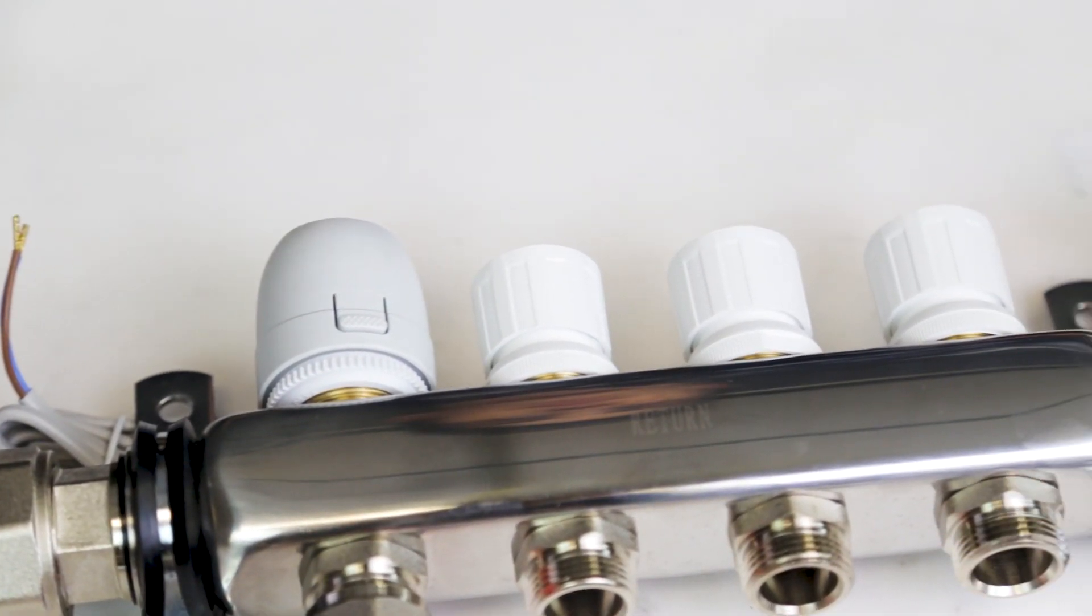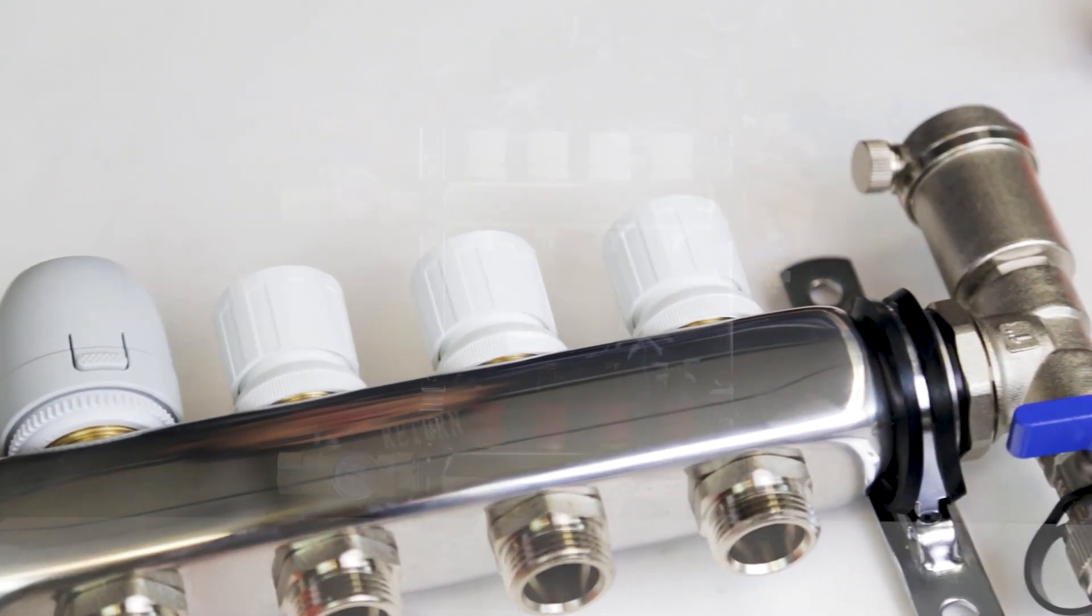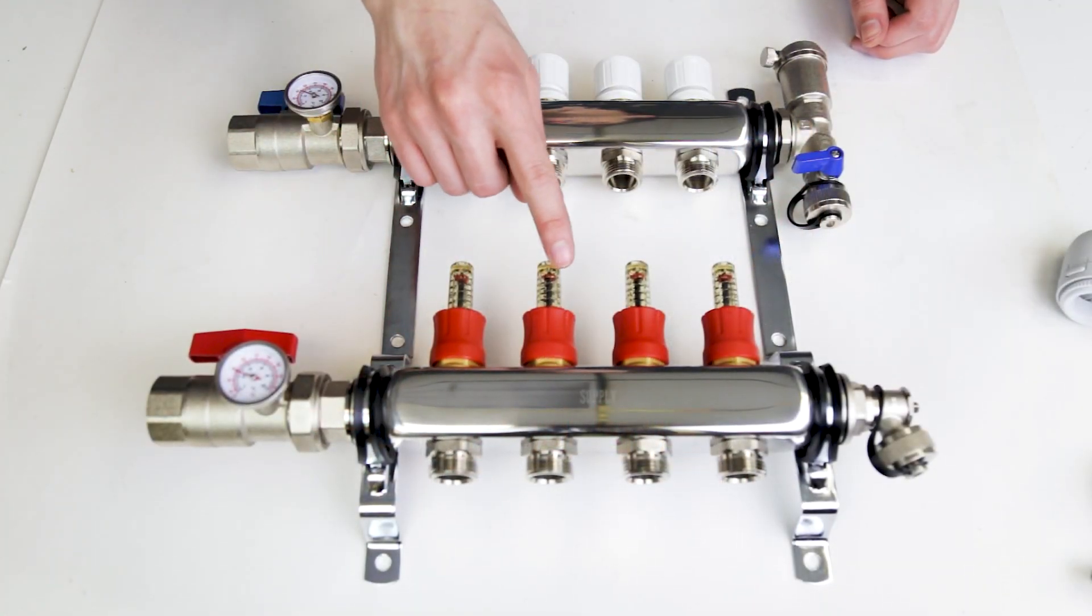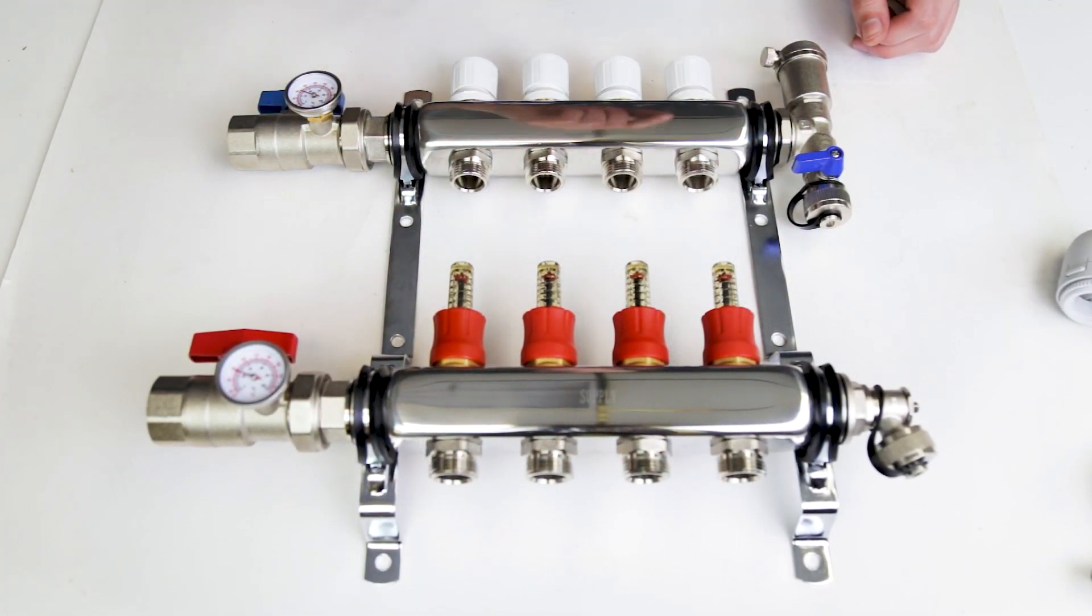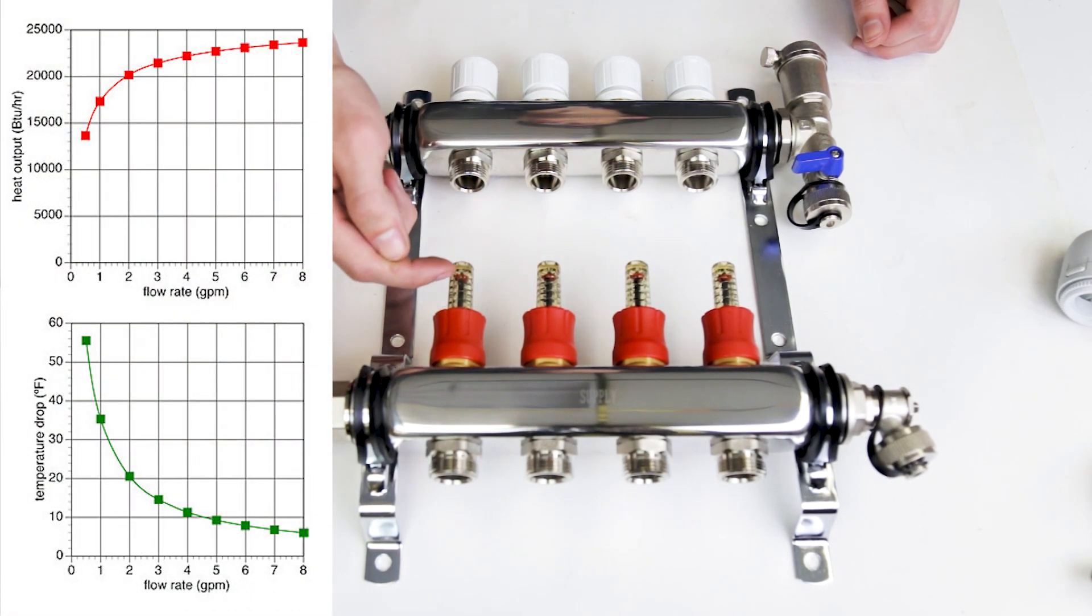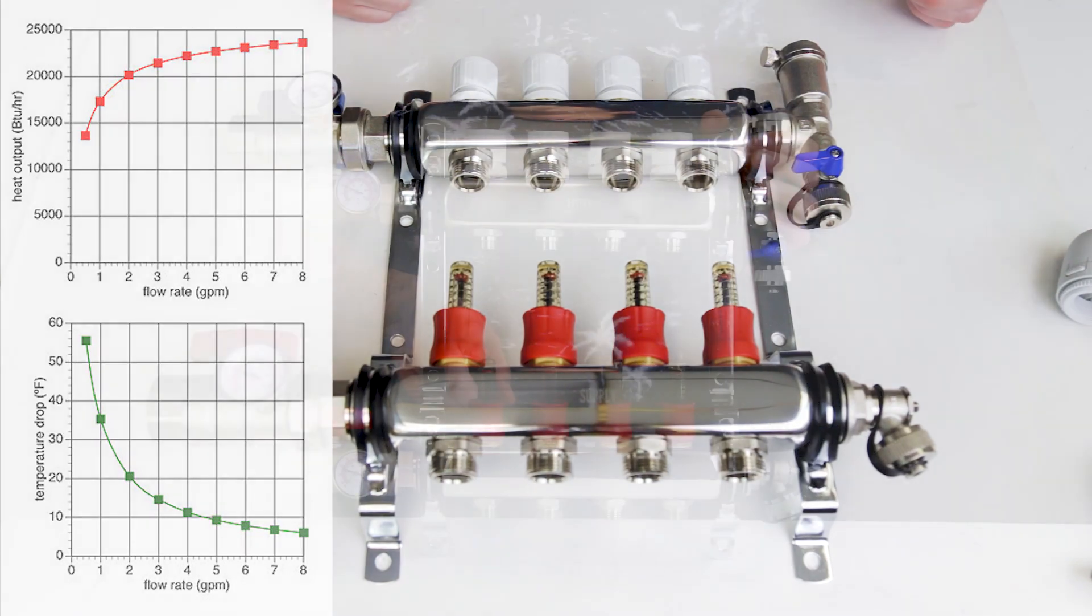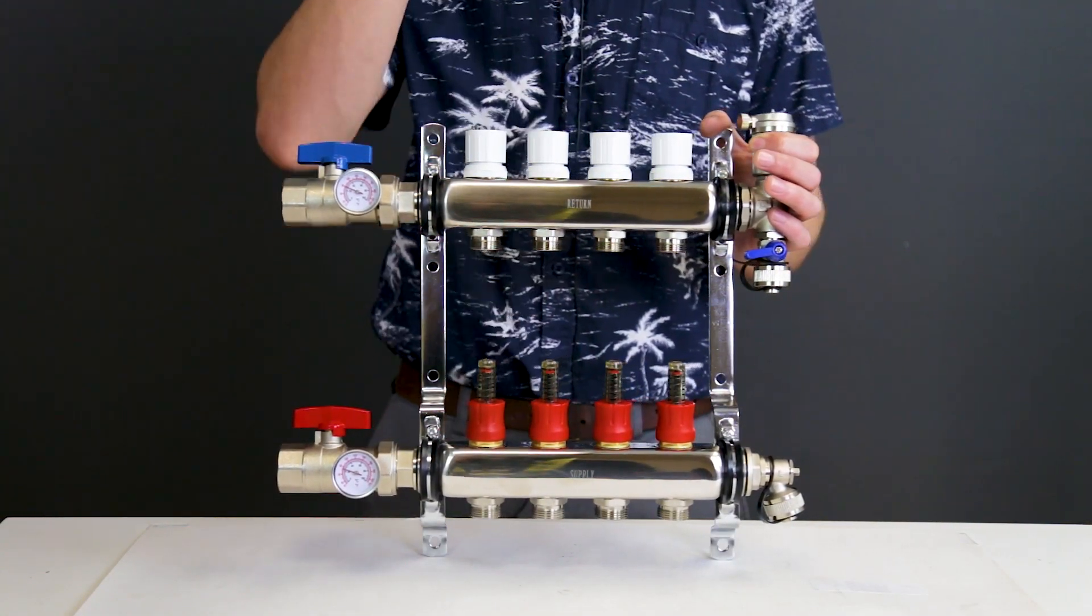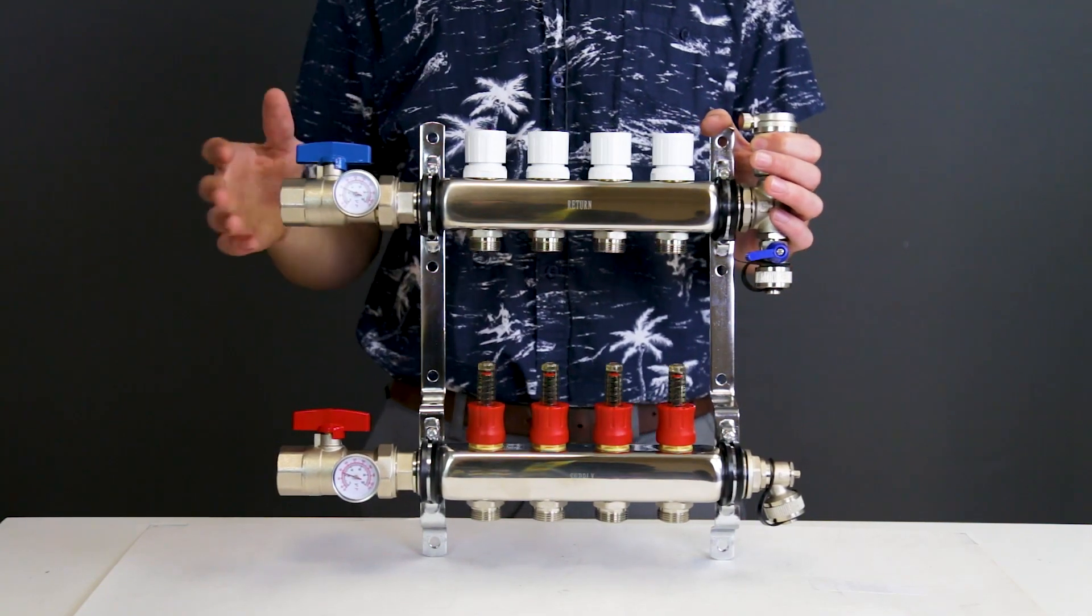The actuators allow the user to control each room or run of pipe temperatures individually. The flow indicators on the bottom of the manifold give a visual gauge as to how much water is flowing through each circuit. The amount of flow needed depends on the length of the circuit and the amount of temperature drop needed. As a rule of thumb, the shorter the circuit, the more restriction that will be required. This is how you balance the system.